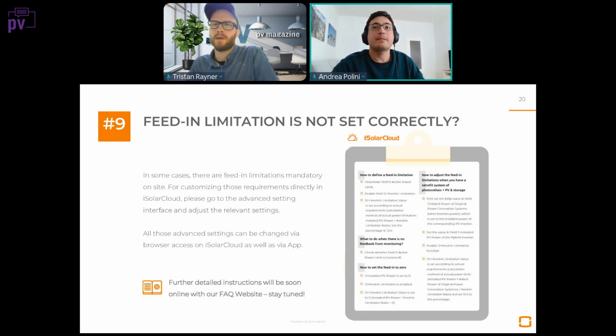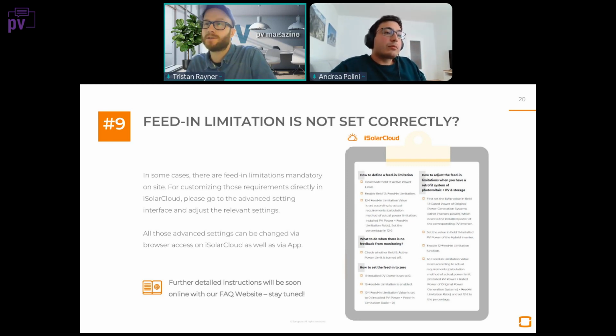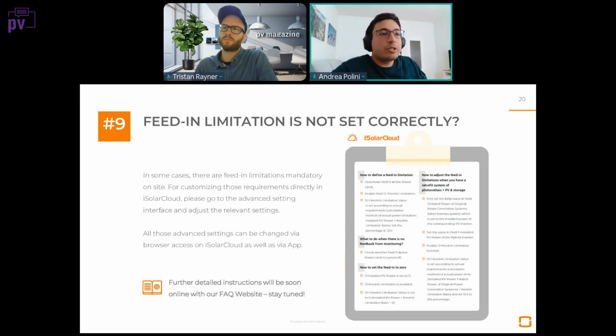Okay, and just a question that's come in from the audience on this: can the feed-in limitation be set to 0 per phase, as opposed to the sum of the phases? Unfortunately, not. This is not a software limitation, rather a hardware limitation, meaning our inverter is balanced, so every phase provides the same power, except if you are in backup mode, of course. In backup mode, every phase can be different. But in grid following mode, every phase provides the same power. So we cannot do feed-in limitation independently for each phase. I know this is a requirement for some East European countries.